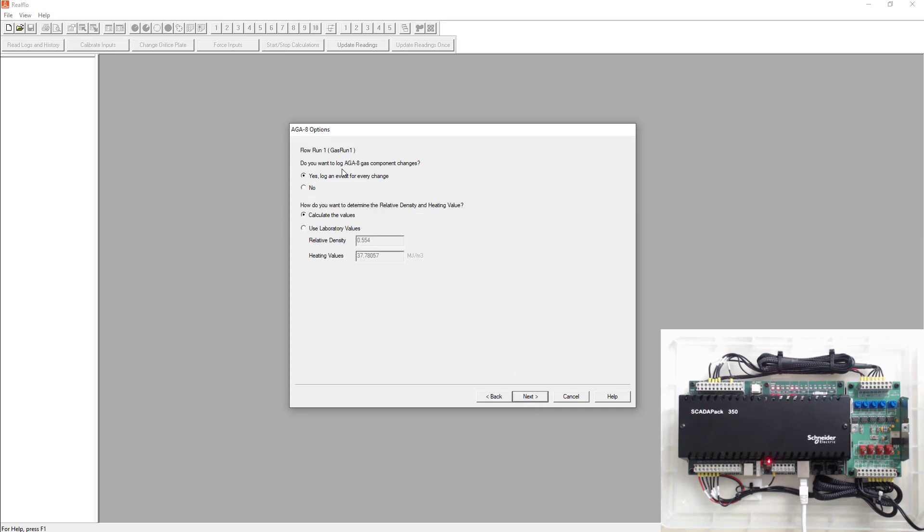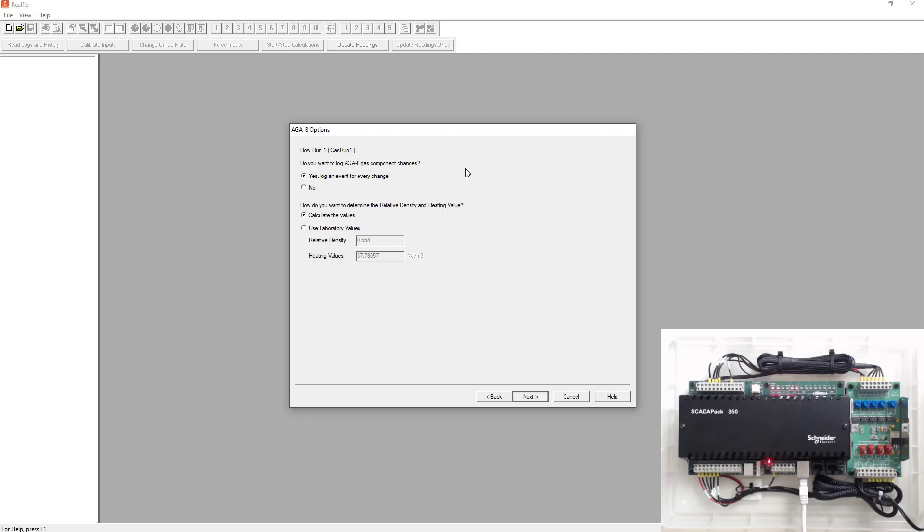Next is going to say, do you want to log the AGA 8 gas component changes? So anytime you change the gas component, do you want to log it? We're going to select yes. The only time you select no here is if you have an inline gas chromatograph. So the gas chromatograph's changing the AGA, or the gas component changes live and it's just going to log it all the time and fill up your event log. So you'd select no in that situation, but for our situation, we're going to be typing everything in manually. So we want to hit yes. And we want to calculate the relative density and heating values as well.